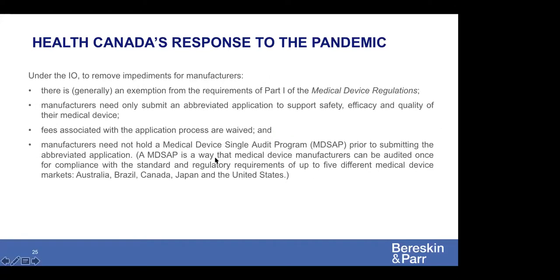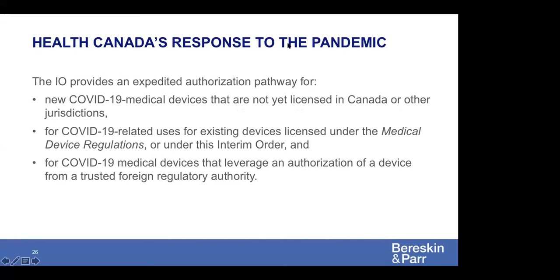Next slide, please. So the interim order is designed to remove impediments for manufacturers of COVID-19 devices. For example, this means that under the interim order, manufacturers need only submit an abbreviated application form to support safety, efficacy, and quality of their device. And all fees associated with the application process are waived. Next slide, please. The interim order provides an expedited authorization path for 3 types of devices. So the first type would be new COVID medical devices that are not yet licensed in Canada or any other jurisdictions. Devices that are already licensed in Canada, but not for COVID-related uses. And then the third type would be COVID-19 medical devices that are authorized by a foreign regulatory authority, such as one in China.